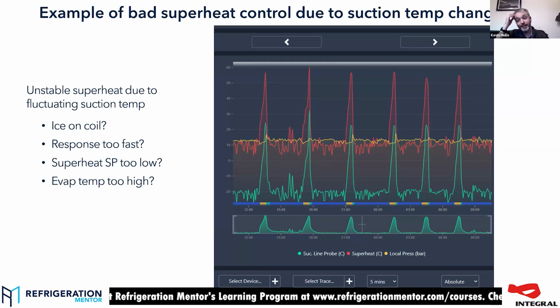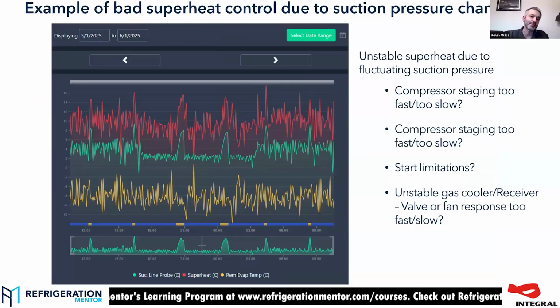No, especially in the CO₂ world where we use thicker pipes, all you're ever seeing with that suction temperature is a time delayed version of reality, because it takes time for the change in temperature of the actual gas to conduct through the pipe and to conduct through the probe. So you're only ever seeing what happened a few seconds ago. And so if you make it too tight, it can't react fast enough to that change because it's seeing it late. It's already got worse or it's already got better before the controller's seen it.